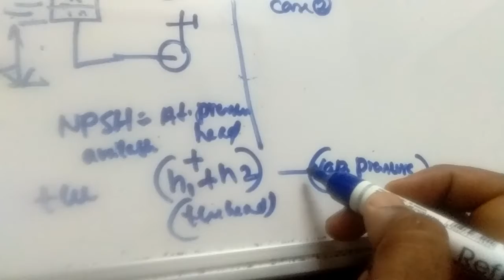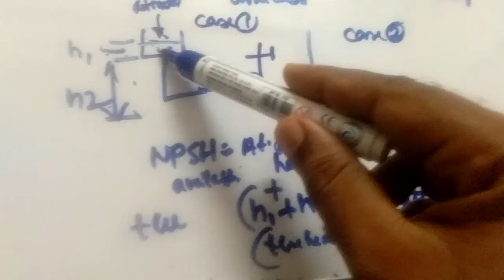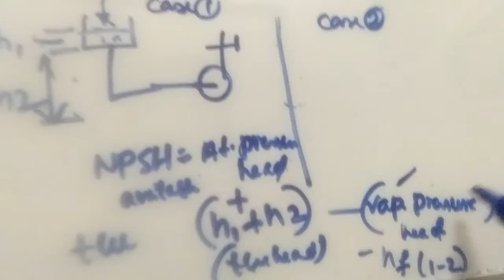All liquids have vapor pressure, and we need to convert the vapor pressure into head terms, vapor pressure head, because in terms of head we need to write. So we need to convert that at particular temperatures. So it is minus, the same conversion. From the water, traveling from here to here, some losses take place, that is major losses. So we can write the head loss due to friction as hf1-2. So this is the formula for the NPSH available.